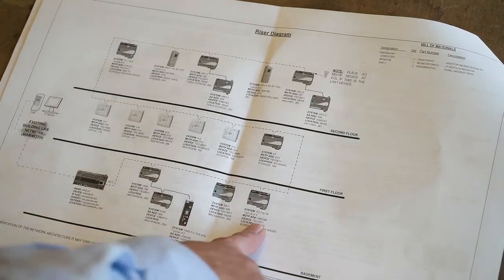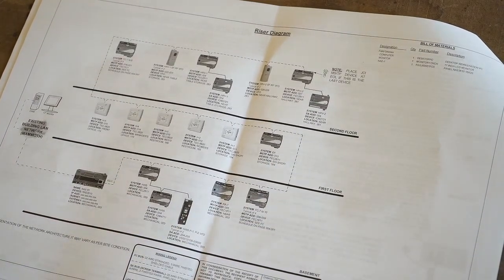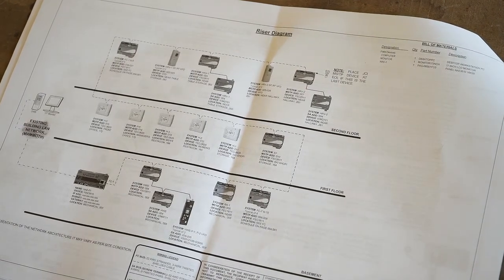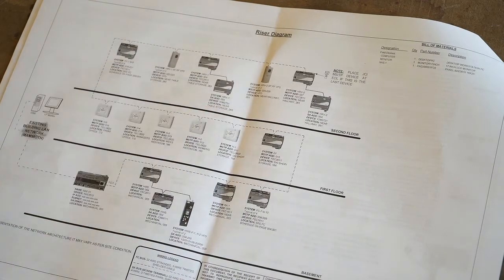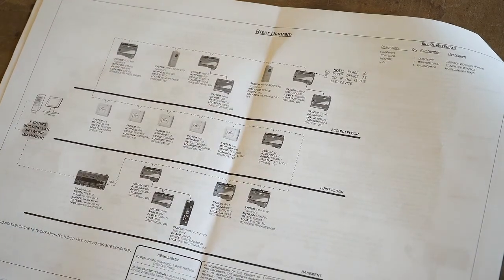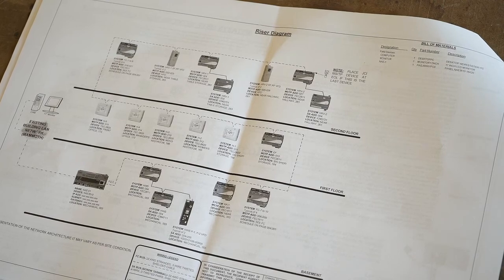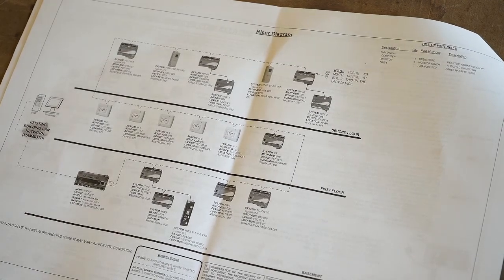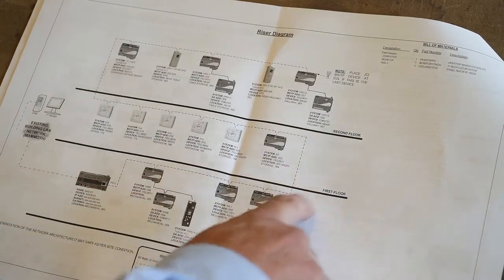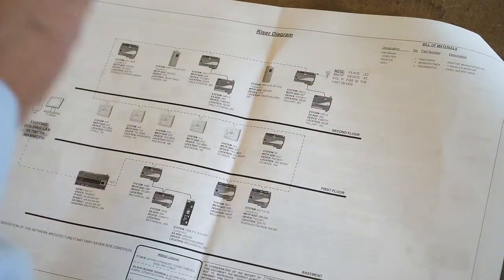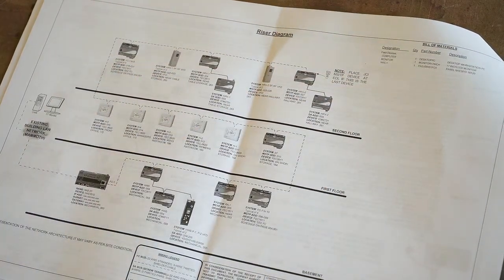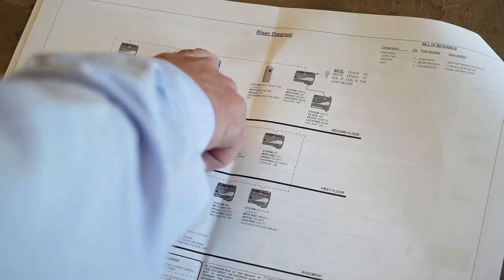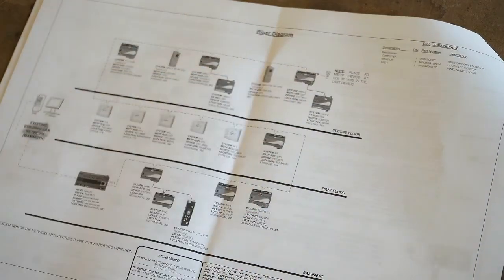And then we've got fan coils. So again, that's the trunk that hits all the devices. We have the two VFDs downstairs on the hot water pumps also pulled in there so we can see amps and everything off of those also. So this is a handy list to go through because it shows you all the connections. So if you go into a system and part of it's missing, it'll give you an idea where to start looking to where that line's cut or been damaged.